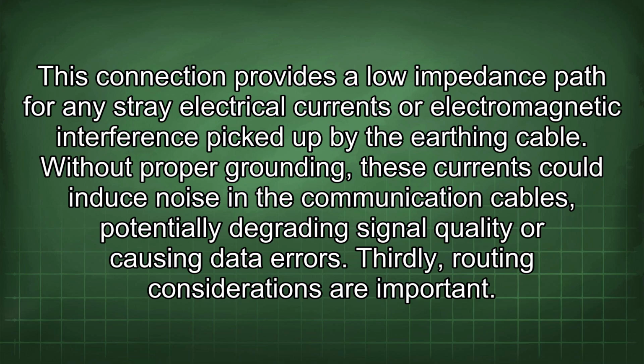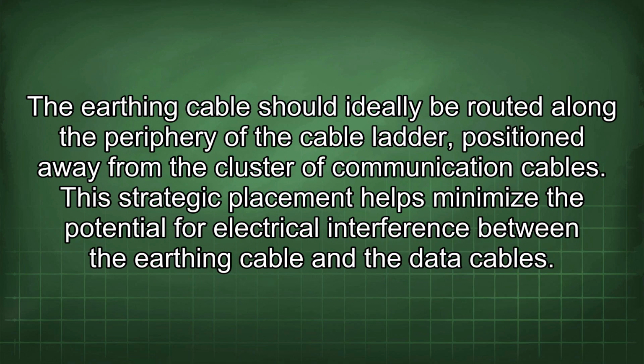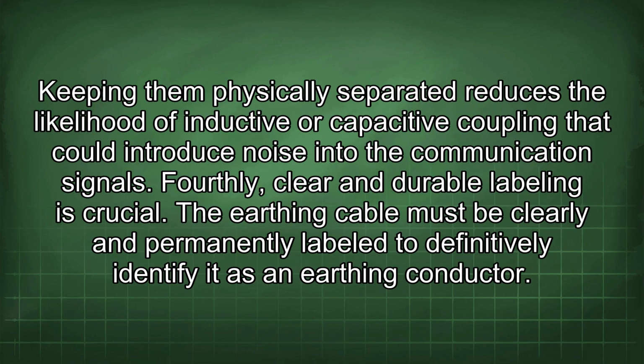Thirdly, routing considerations are important. The earthing cable should ideally be routed along the periphery of the cable ladder, positioned away from the cluster of communication cables. This strategic placement helps minimize the potential for electrical interference between the earthing cable and the data cables. Keeping them physically separated reduces the likelihood of inductive or capacitive coupling that could introduce noise into the communication signals.